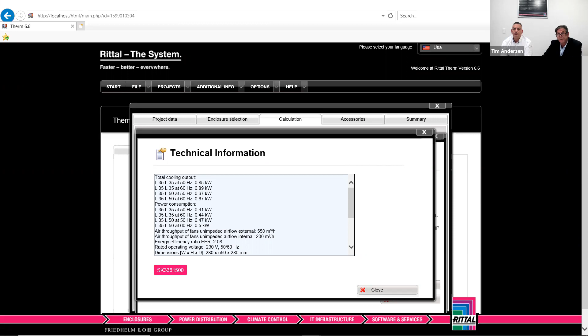So do you see that even though this unit can produce 0.85 kilowatts on a 35-degree day, at 50 degrees it can't get near there. It's more likely to be 0.67. So that's why it's so important that you put the right variables in that beginning screen, even though you can change it later. Now, the units it's picked at the bottom are, won't say the low end, but the industrial range of Rittal's basic range, which you call the Blue E or Top Therm.